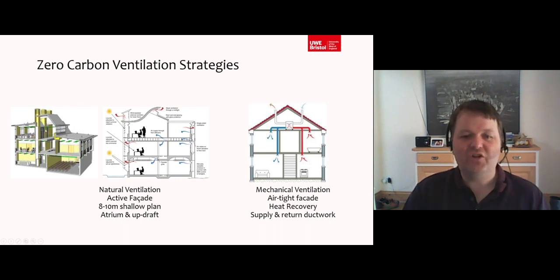It may be that the calculations show this is quite a complex design. Natural ventilation calculations may show that at the worst time of year you may need a little booster air, so you may put in a fan or two just to cater for that worst case scenario. Especially with the 3 examples I gave of a studio space or an office, a computer room, and a classroom, because of the densities in there, your computer room with lots of students, that might actually be a scenario where you'll say, I'll put a little booster fan on that just for those worst case summer days where, with the computer heat and the people heat, the load is just not sufficient to be met by the actual draw of the building. So that's the ventilation strategy.